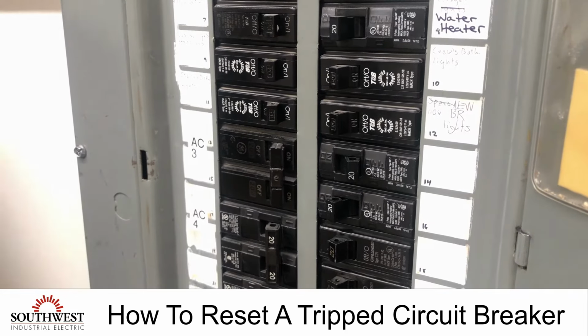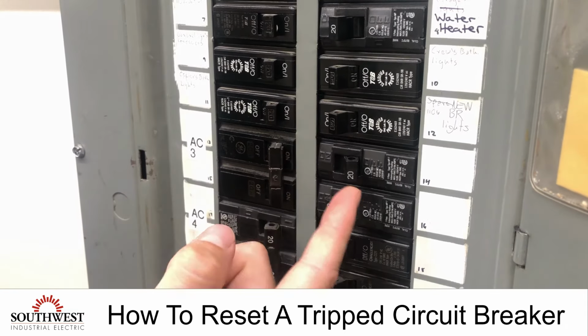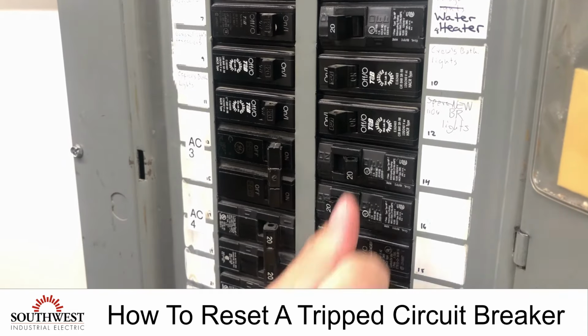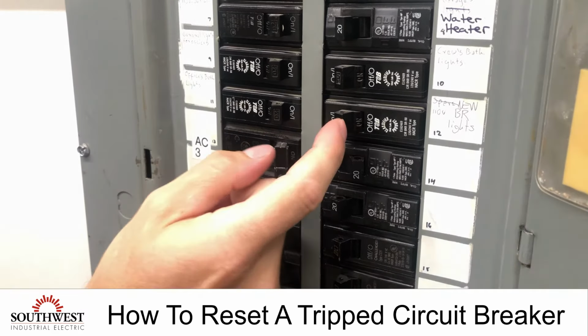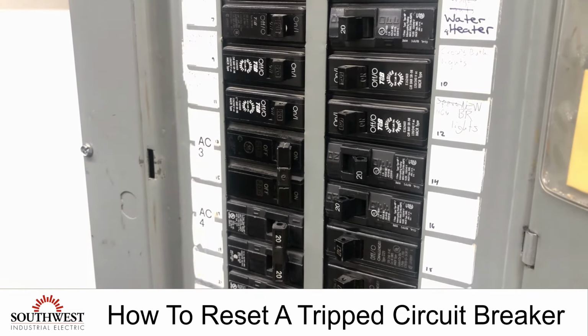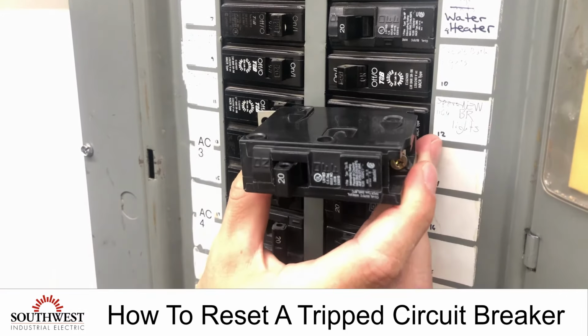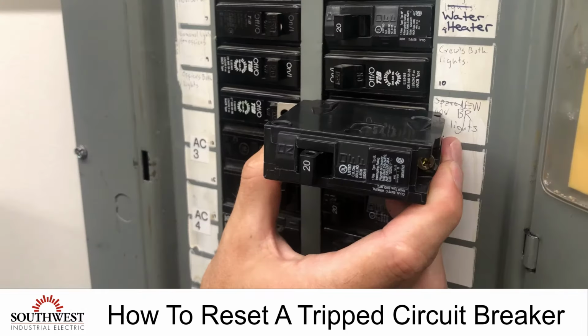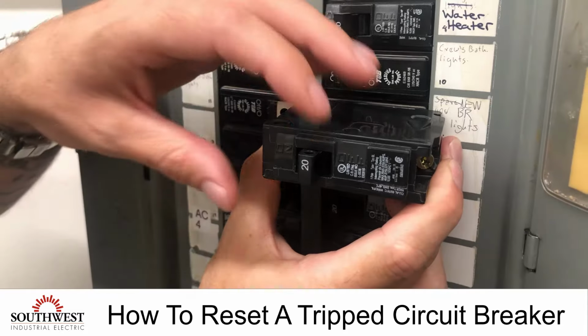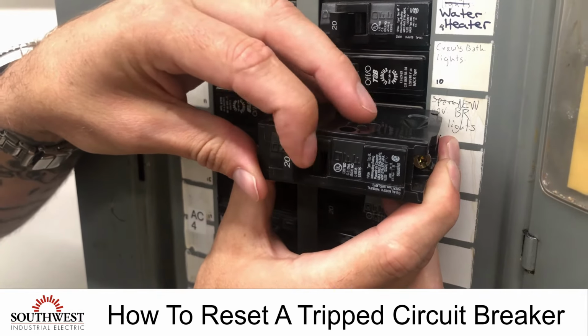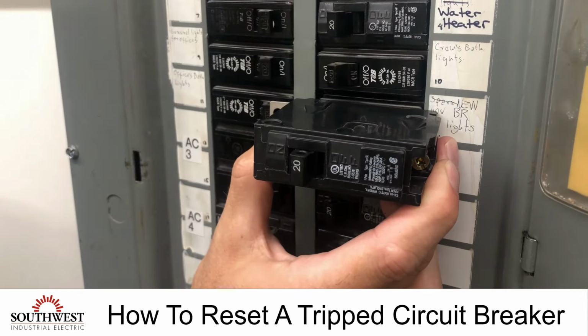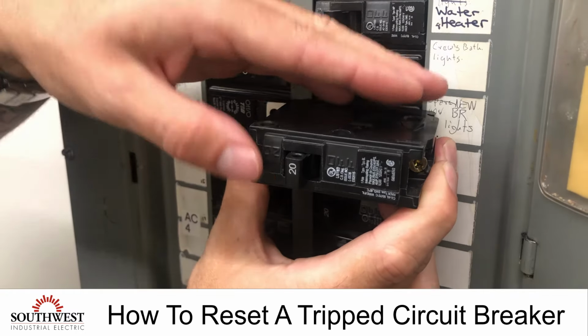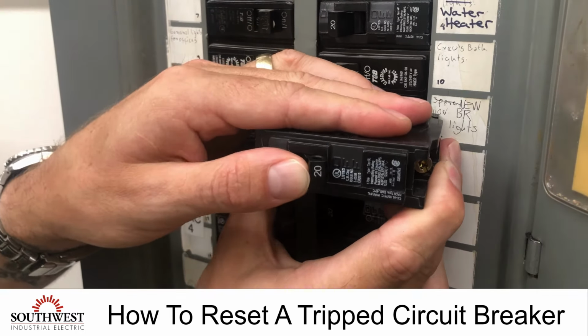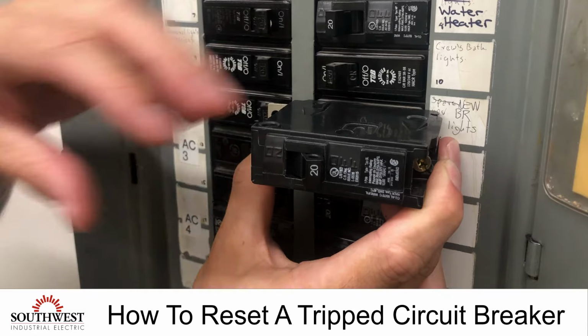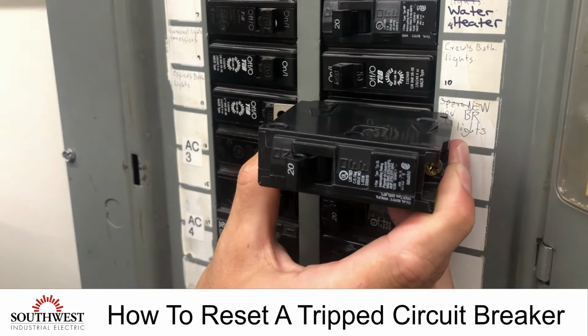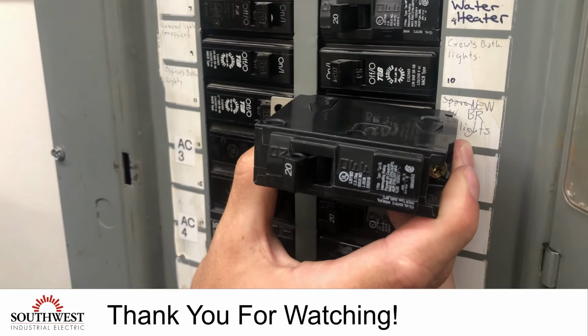Breakers have two positions, on and off. Off is fully off, on is fully on. But when a circuit breaker trips, it actually goes into a center position. When you try to turn this circuit breaker on, the handle will spring back. To reset this breaker, you need to push it all the way to the off position until it clicks, and then you can turn it back to the on position. That's how you reset a tripped circuit breaker.